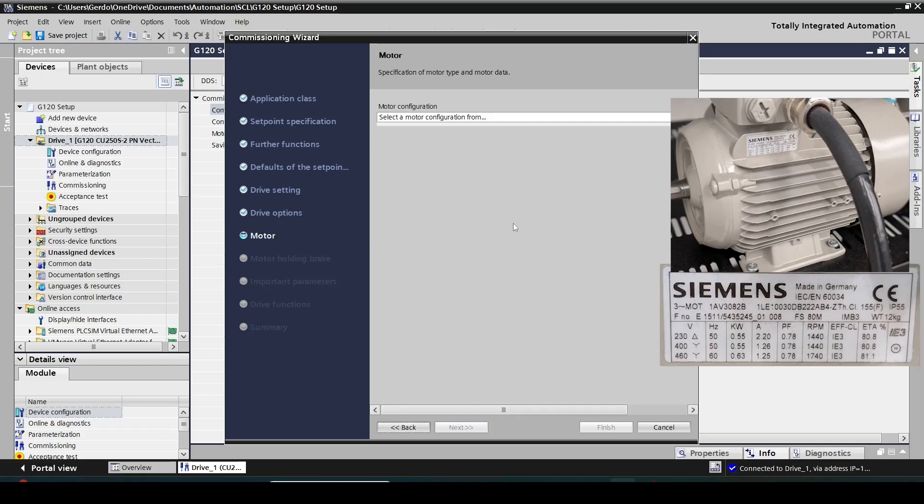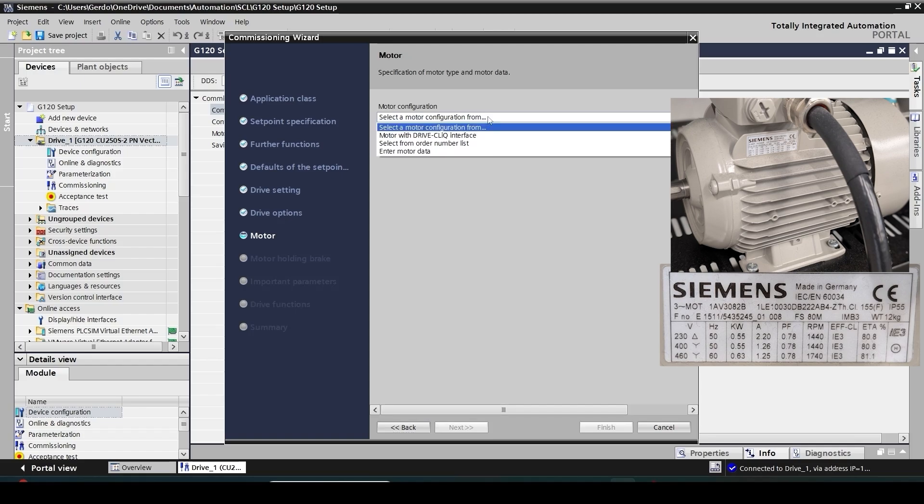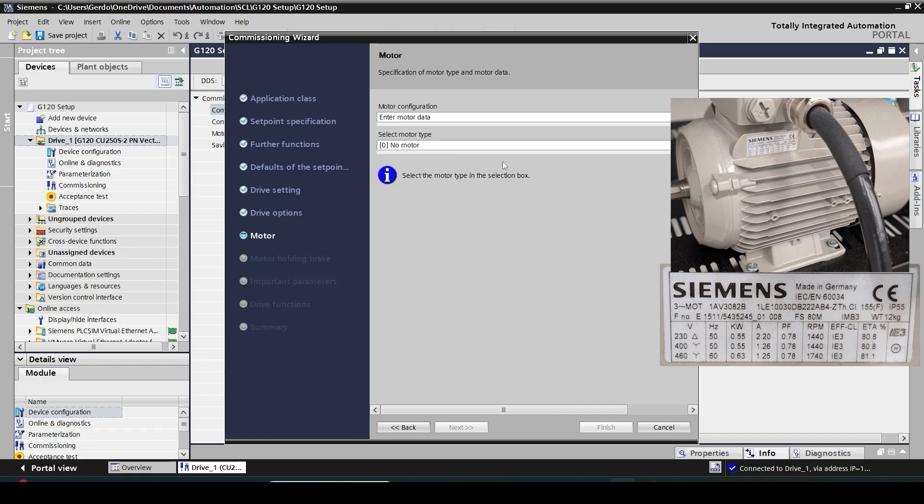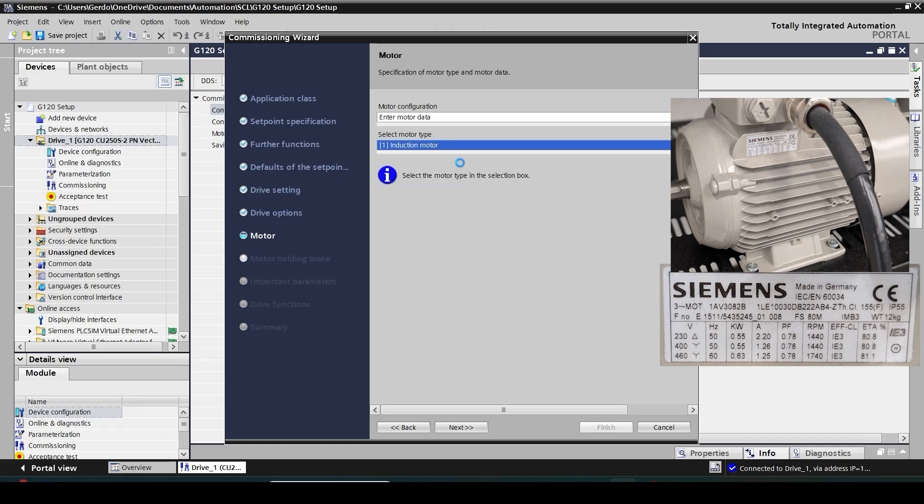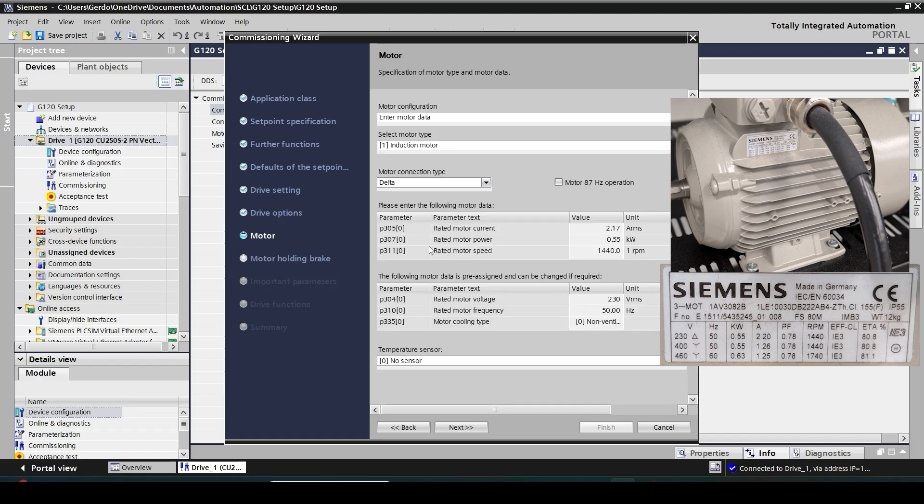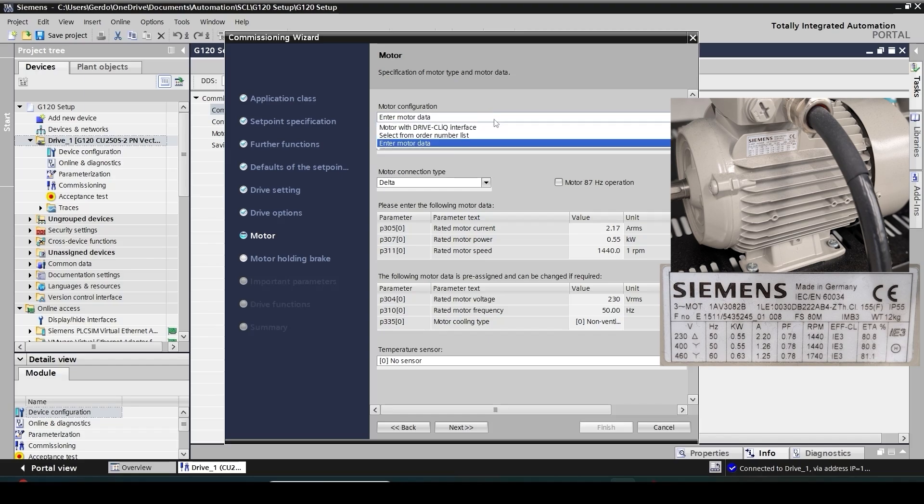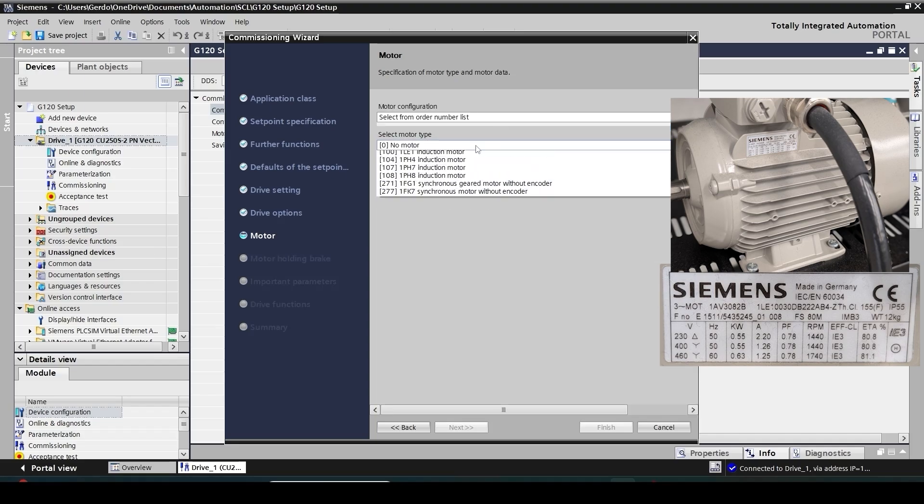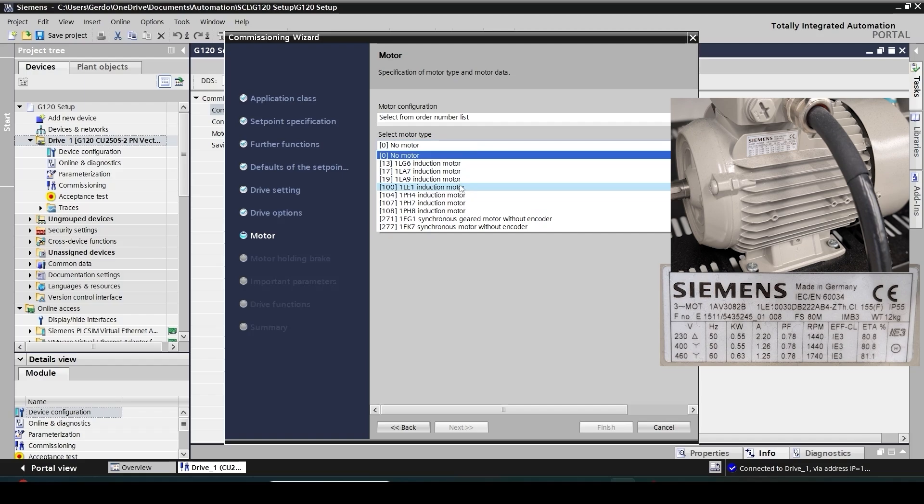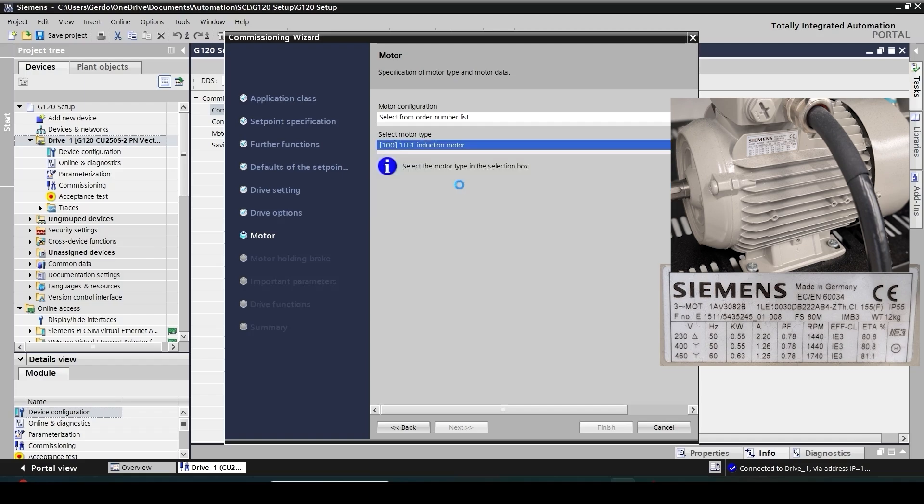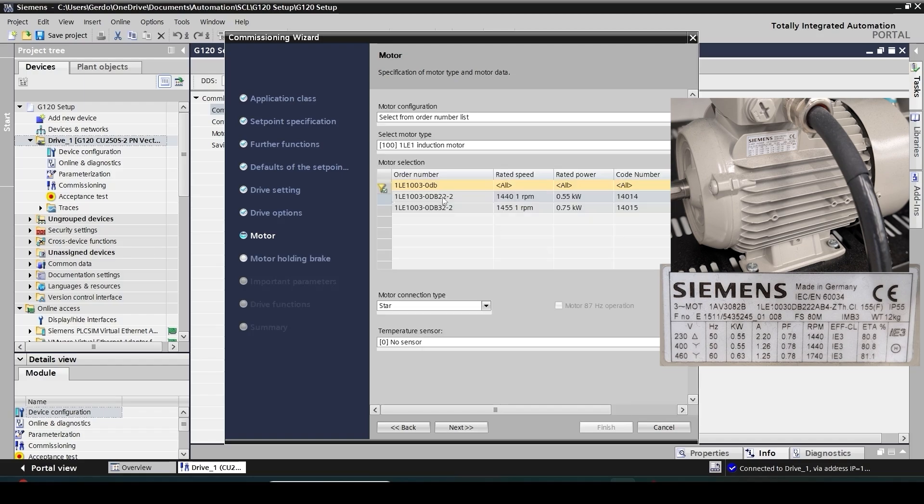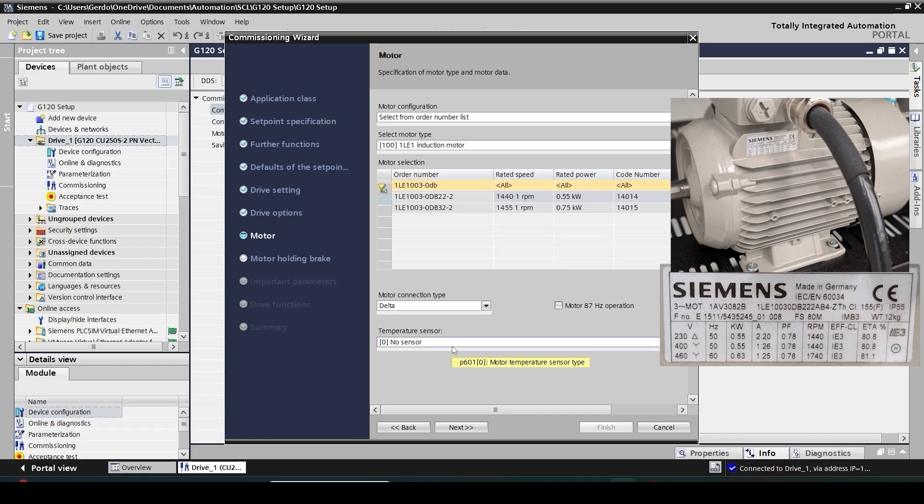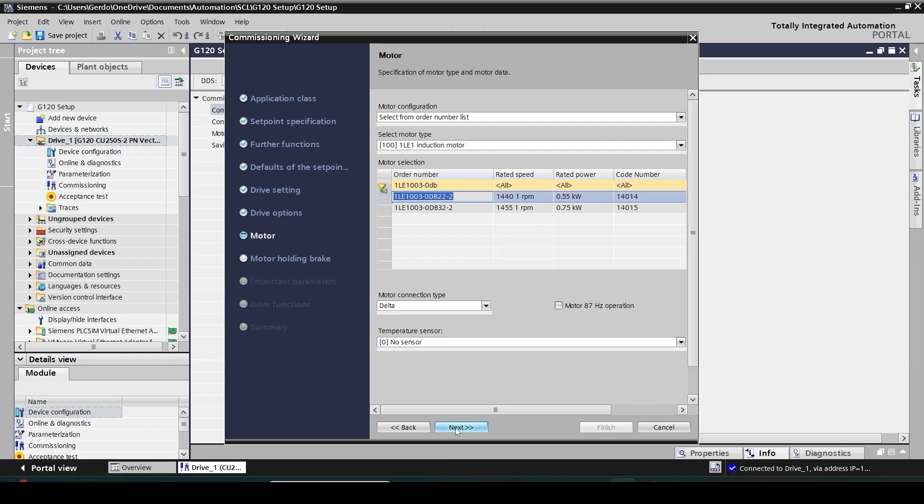Next you need to specify the details of your motor. You either have a Siemens motor or a non-Siemens motor. If it's a non-Siemens motor then you need to pick enter motor data, and then you specify induction motor and then you put all the details here. You can find this information from the motor's nameplate. If it's a Siemens motor then easiest way is to specify the part number and then all the details would be loaded automatically. So I select here, select from the order number list, and then I have a 1LE1 series and I know that I have this motor. From the wiring standpoint I know that I have wired my motor in delta configuration and then I have no sensor. That's it.